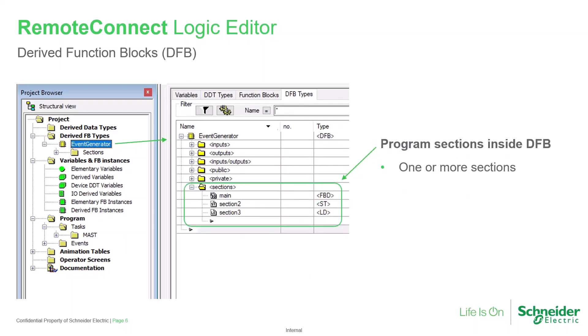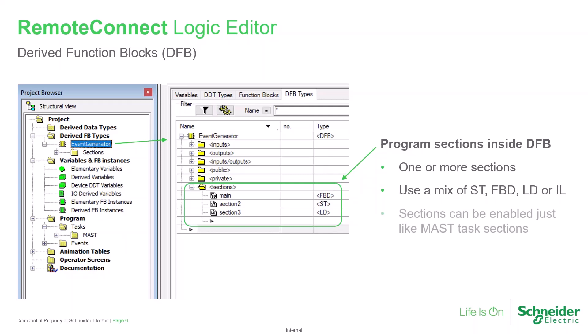A derived function block may be built with one or more logic sections, allowing functionally different logic to be kept separate. Each section may be developed with any of structured text, function block, ladder diagram, or instruction list, whichever is most suitable. These sections may be enabled or disabled with a control object, just as main program or MAST logic sections can be.